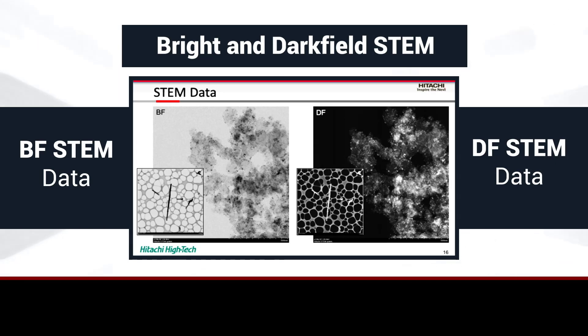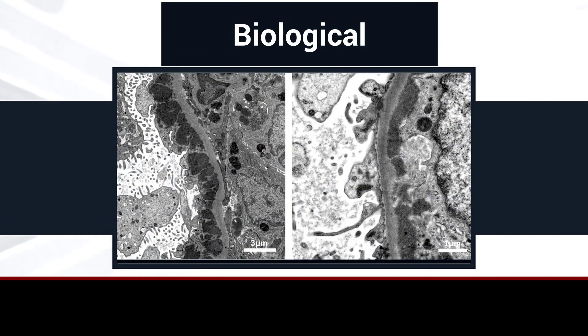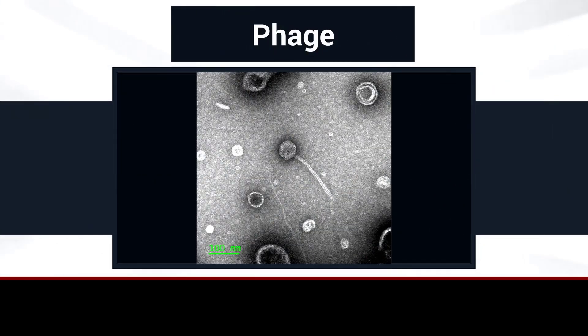Simultaneous bright-field and dark-field STEM, coupled with EDS, adds new dimensions to the analytical capabilities of the HT7800 series. In addition, flexible mounting positions are available for high-resolution cameras. Bottom, direct, and side-mount orientations allow versatility for desired imaging applications.